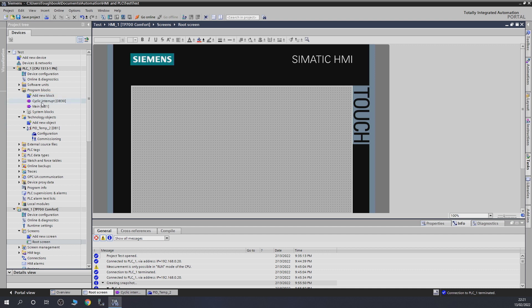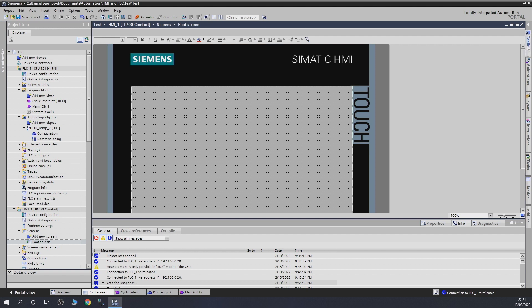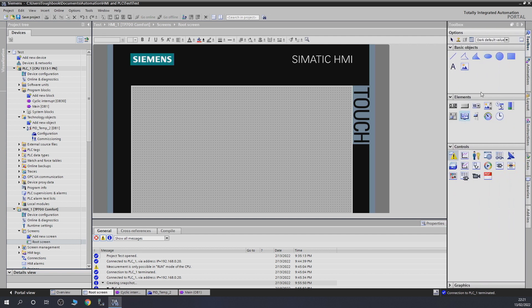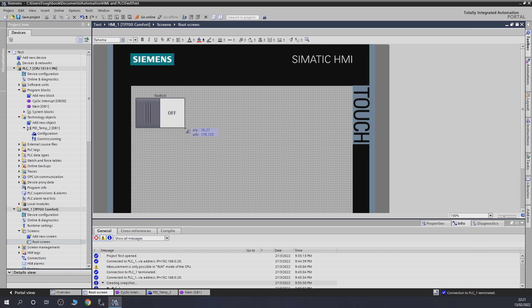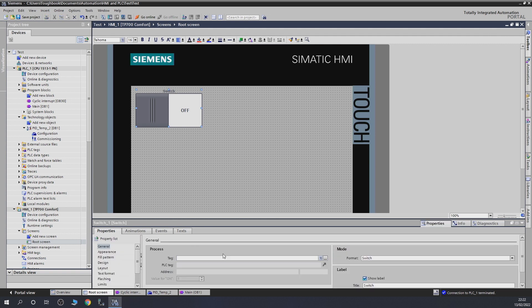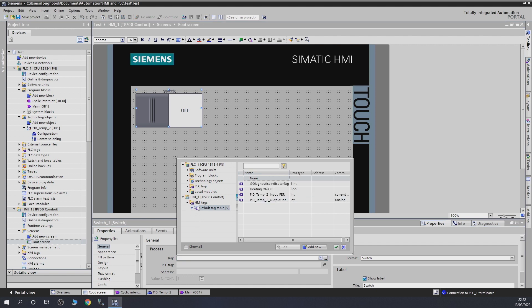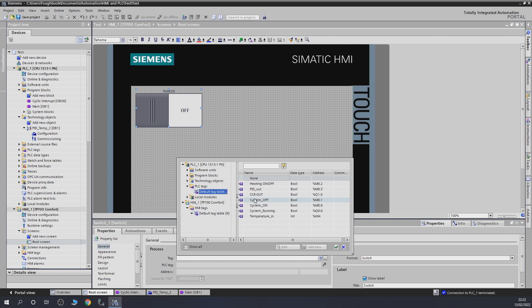The first thing we need to do — if you remember from the last video — is put a switch on our HMI screen. We have our PID out, our switch on/off, and the SSR out which goes to a digital output. Let's jump to the root screen and add the switch from the toolbar. Let's grab a tag and go into the PLC tags — we need 'Heating On Off', that's the one for that.